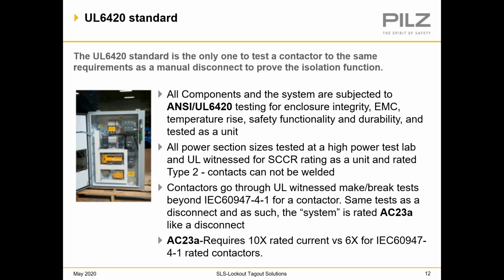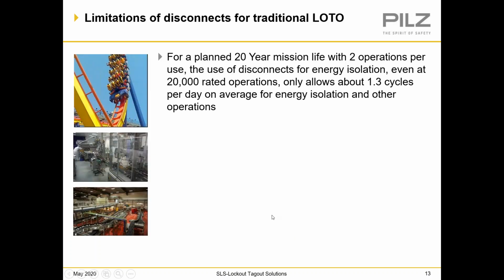And so these are some of the issues associated with upgrades of a contactor to make sure that it meets the 6420 standard, the AC23A rating. So what are some of the limitations here? Well, for instance, if you are using a disconnect as your source of lockout, a disconnect has roughly 20,000 rated operations maximum. And for each lockout that you use, that's 2 operations, an off state and a back on state.